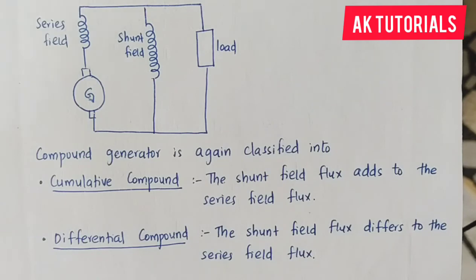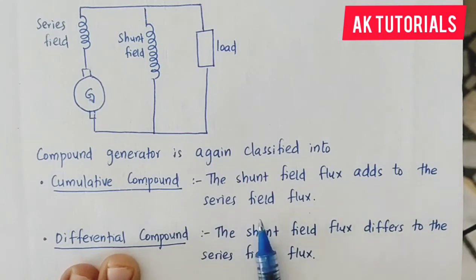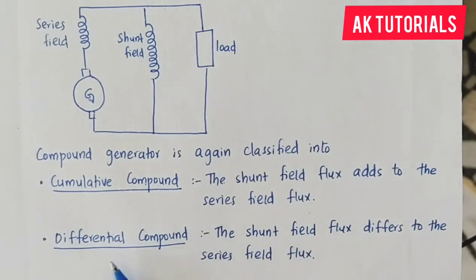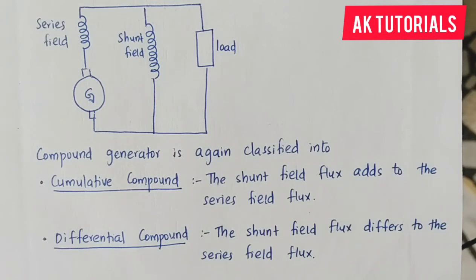In cumulative compound, the shunt field flux adds to the series field flux. The differential compound is the opposite: the shunt field flux is subtracted from the series field flux — that is, shunt field flux minus series field flux. That type of generator is called differential compound generator.